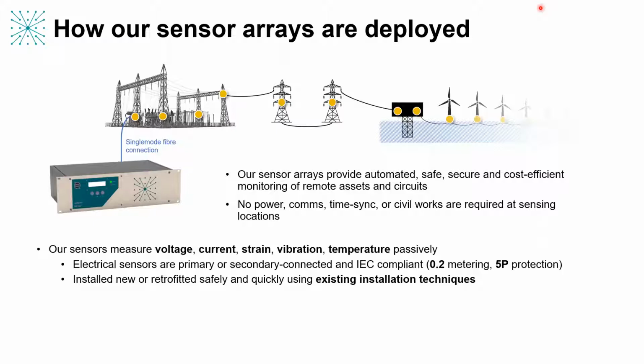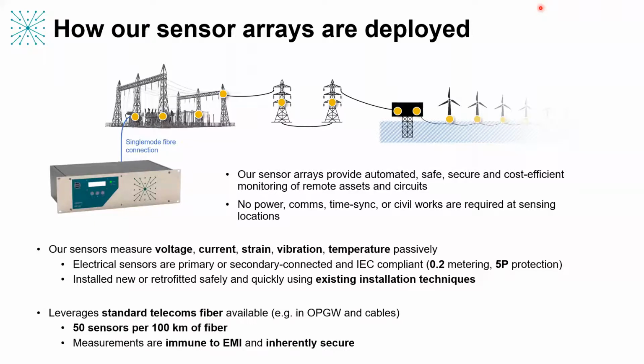Now, the way that we install these sensors is very like typical CTs and VTs, except that the installation procedure no longer involves copper secondaries. So there's none of the traditional safety requirements that you would need for having live copper secondaries and having an outage there. If we can go around an insulated cable, for example, then that is a safe installation procedure because we have no copper secondaries. Everything is connected by optical fiber.